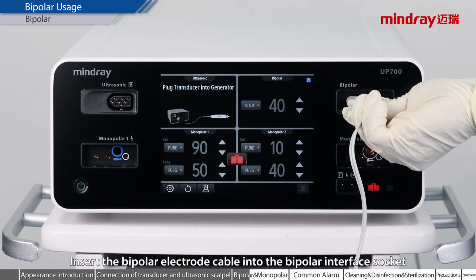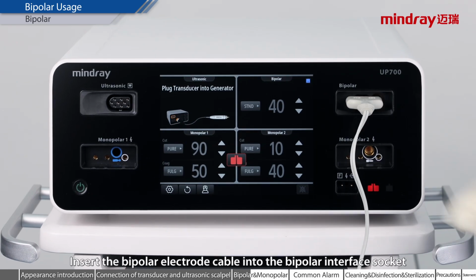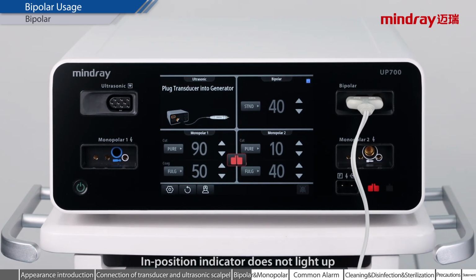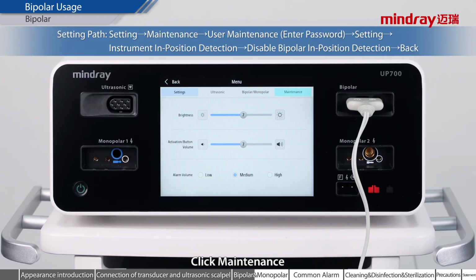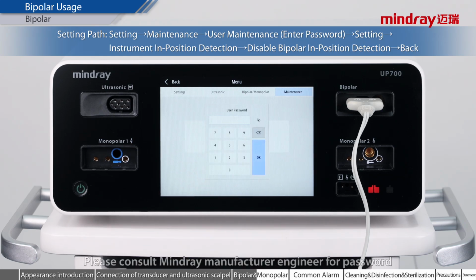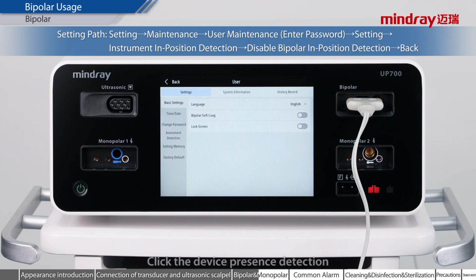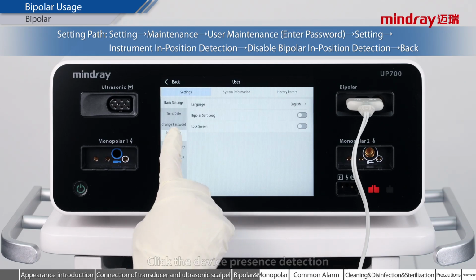Insert the bipolar electrode cable into the bipolar interface socket. The in-position indicator does not light up. Click Setup. Click Maintenance. Click User Maintenance. Please consult the MindRay manufacturer engineer for the password. Click the device presence detection.